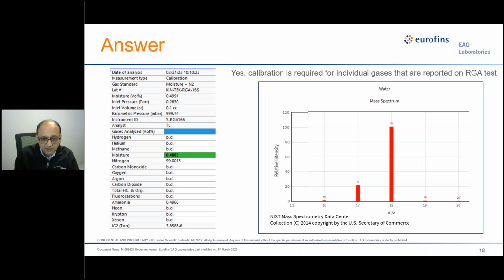So when you introduce the moisture into the mass spec, and as we talked earlier, the moisture will be ionized. And when you ionize the moisture, you will have fragments of it. And this NIST mass spectrometry database is showing moisture would have mass 17 with almost 20% contribution, and less than 1% contribution for 16, 19, and 20. Now, mass 18 is the mass that we will use for determining the moisture content.